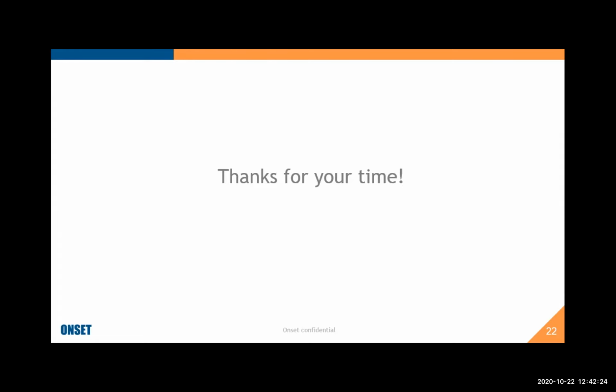While you guys are thinking of questions, there was one question I noticed in the questions you guys sent in advance. So thanks for sending those. I think we tried to cover some of those in the presentation, what Andrew was covering. But one of you asked about how to get temperature accuracy improvements, because you were doing a temperature chain sort of application. I wanted to address that because Greg Sinnett, who was doing the research on the Scripps Pier there, individually calibrated each of the loggers. He had, I think, 36 temperature loggers at different depths and different distances from the shore. And what he would come up with is an individual calibration offset for each of those loggers.